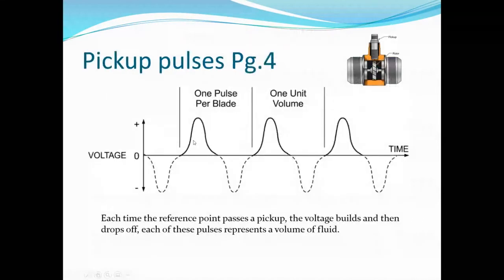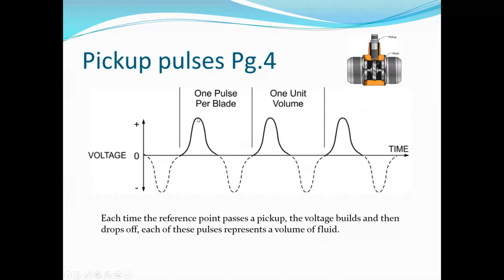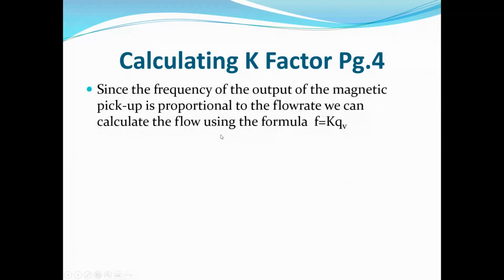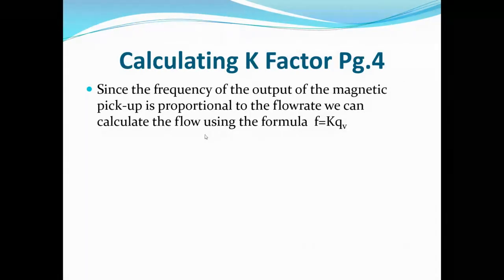As the rotor spins, it approaches and then moves away from the pickup, generating an oscillating sinusoidal wave. Every time the detector senses a blade coming closer, it counts it. That voltage building up and dropping off represents a specific volume of fluid — one pulse represents a specific volume. We can calculate volumes based on the number of pulses, and the frequency of the magnetic pickup output is proportional to the flow rate.